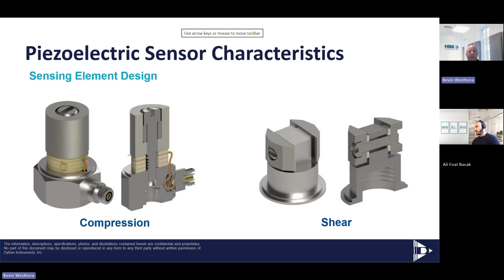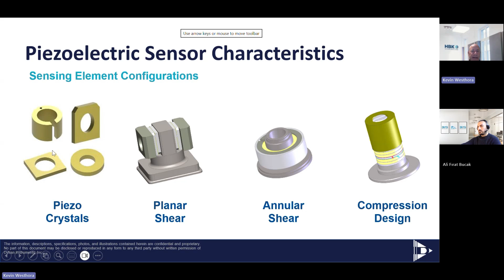The crystals come in all shapes and sizes, depending on the application, the sensor, etc. But over here on the left is what a piezoelectric crystal looks like once it's been cut, then polarized, and then cut again for mounting into the accelerometer, depending on what size. That's what they look like. This is a good cartoonish depiction of what's happening with a piezoelectric IEPE shear mode accelerometer.